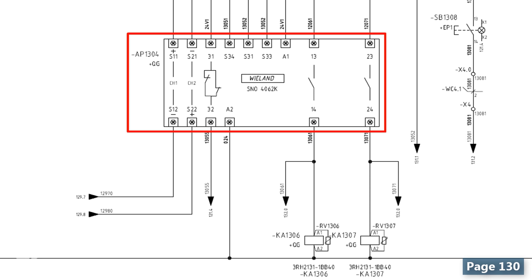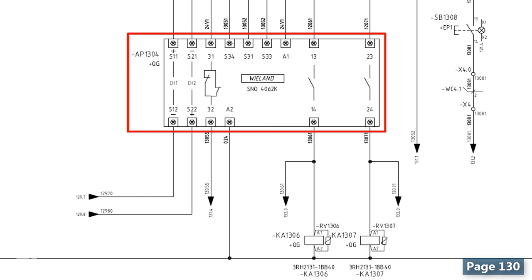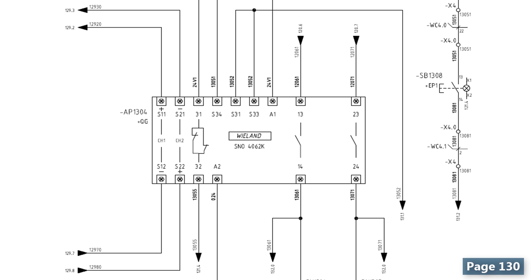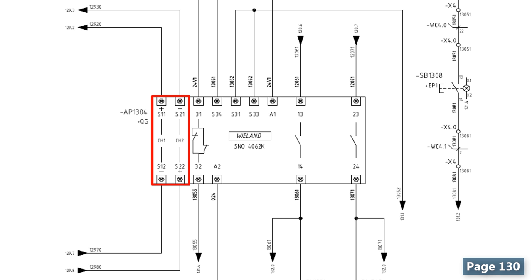In this page, we have a safety relay here and it will be used to protect people, material and the machine itself when the machine is operating. Remember that the designer of this wiring diagram had to refer to the datasheet of this equipment to complete his job. In fact, this is a very important and inevitable stage of designing a wiring diagram and we should always do the same thing for the rest of the equipment used in the process. By the way, these two channels are used to be connected to the safety components at site. For example, the safety barriers.